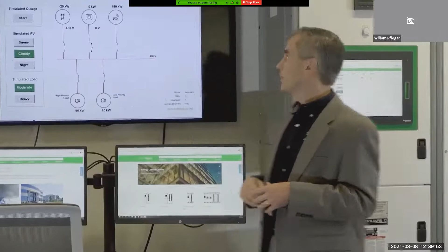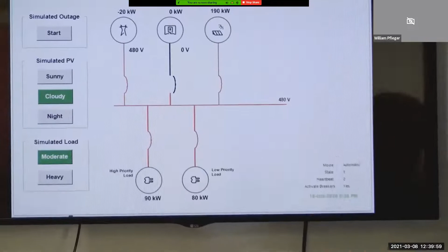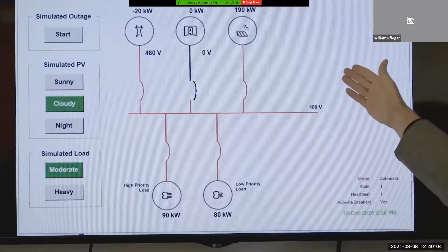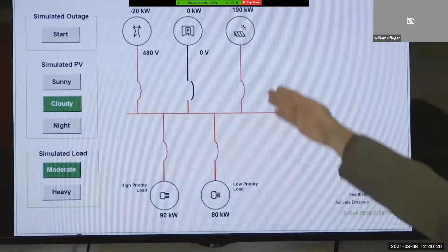So in this initial condition, you can see our utility is here. It's 480 volts. And it's a cloudy day, so our 350 kilowatt array is putting out 190 kilowatts at this particular moment. And that 190 kilowatts coming from the solar array is actually more than the 170 kilowatts of load attached to the ECC. So 20 kilowatts is actually flowing backwards out the main breaker of the ECC and into other parts of the building.